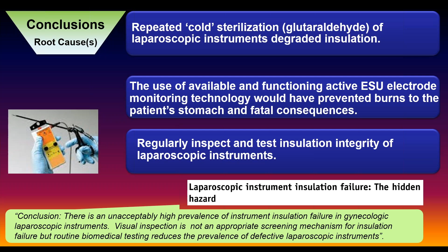And if they had used it, that type of injury would have been prevented. The CS people - I don't know how many places are doing this, but one of the papers I came across showed something like 15 to 20% of the laparoscopic instruments tested had failures in the insulation, just from this repeated cold sterilization.